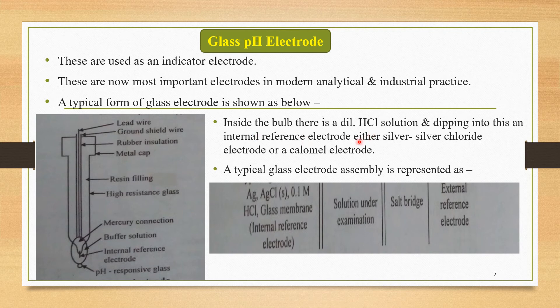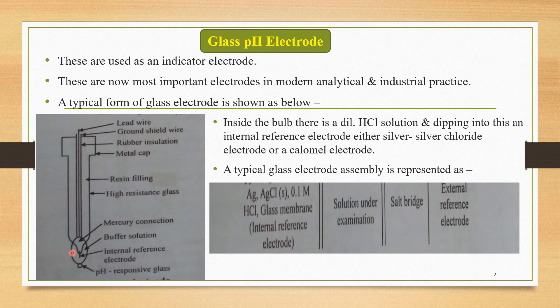Inside the bulb, there is a dilute HCl solution, and dipping into this is an internal reference electrode — either a silver-silver chloride electrode or a calomel electrode. Thus, inside the glass bulb there is a dilute HCl solution together with an internal reference electrode, forming a complete cell inside this particular glass bulb.